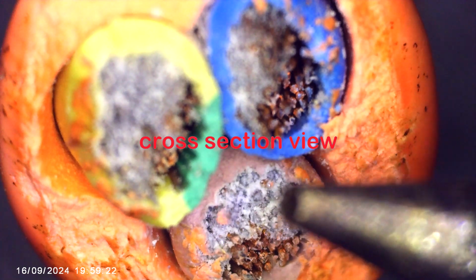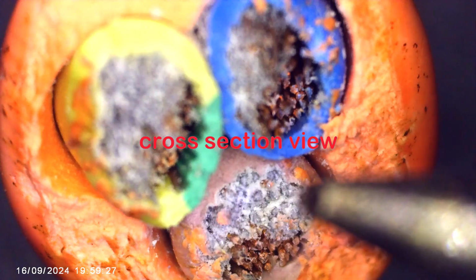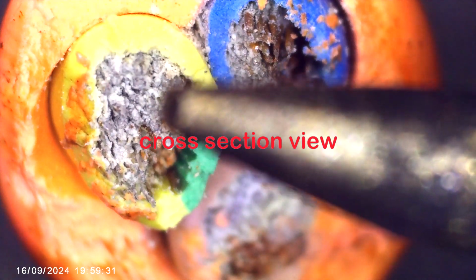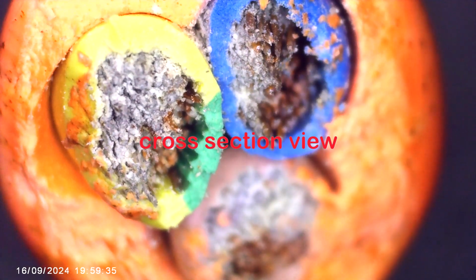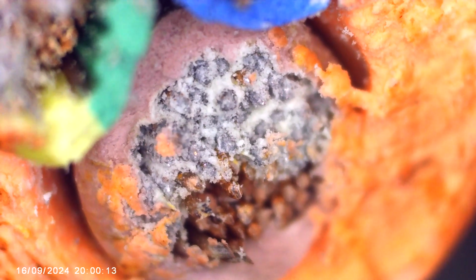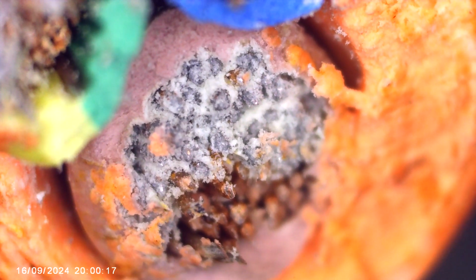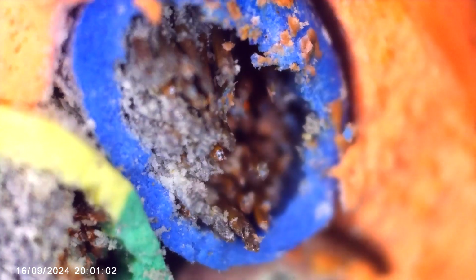As you can see, oxidation has taken place for all the different wires, typically for the live, neutral, and earth. Under higher magnification, you can see that only a certain part of the wire is still copper, and the whitish part has all been oxidized.